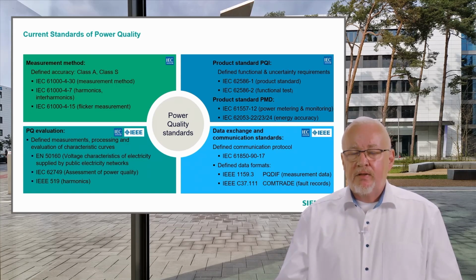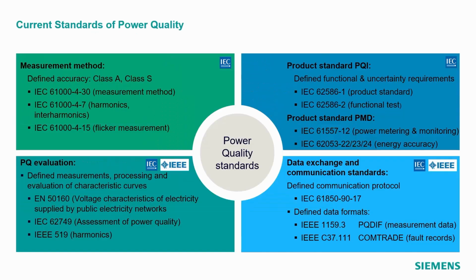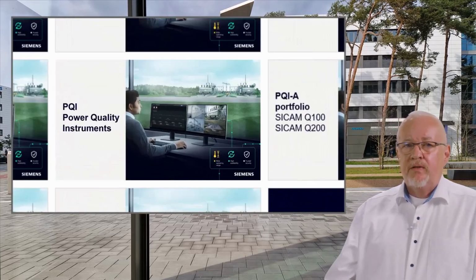And the fourth block in the standardization framework are the communication standards and data formats and data exchange formats. There we have IEC 61850-90-17. It's a technical report which describes using IEC 61850 to transmit power quality data, and IEEE 1159.3, which is meanwhile also an IEC standard, and IEEE C37.111. It's also an IEC standard, described usually the most important data formats like PQDIF, Power Quality Data Interchange Format, and COMTRADE for fault records known from the protection already. So then we can move over to power quality instruments.